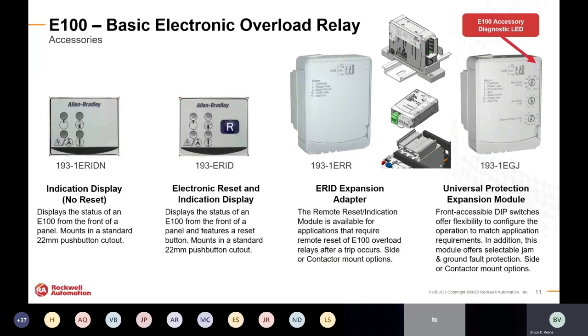With the two ERID modules, that requires the 193 ERR expansion adapter you see in the middle there. That component connects to the E100 through that small expansion port. If you look at the image on the right, you can see the accessory can be mounted on its side, or—something new for the E100—there's an adapter so you can mount this on top of the Bulletin 100C contactor, similar to an auxiliary contact block for that contactor. That's nice to keep in mind if you're looking to save panel space: you can now mount this horizontally on top of the contactor versus vertically on the side, helping save panel space on the DIN rail.